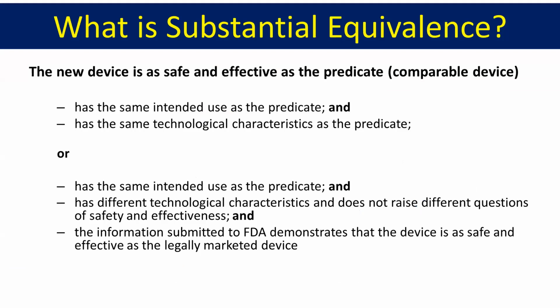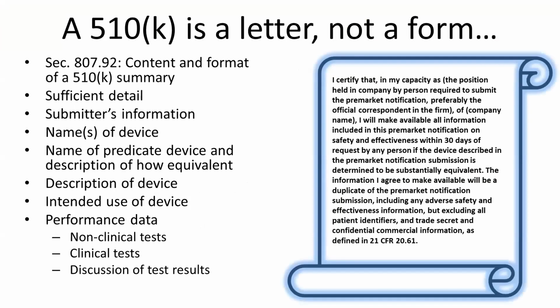So a substantial equivalence is a way of saying that this new device is just as safe and effective as the comparable device. So it has the same intended use and technology, or it has the same intended use, has some different technology that doesn't raise the question of safety and effectiveness, and that you're showing the FDA through some data that that's true. And a 510K is a letter.